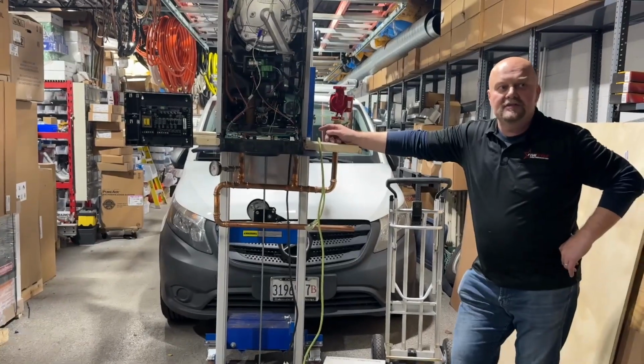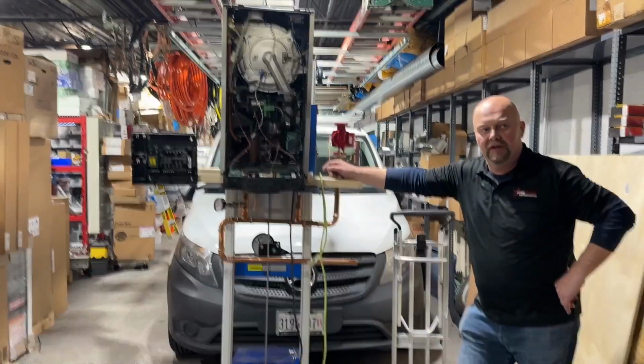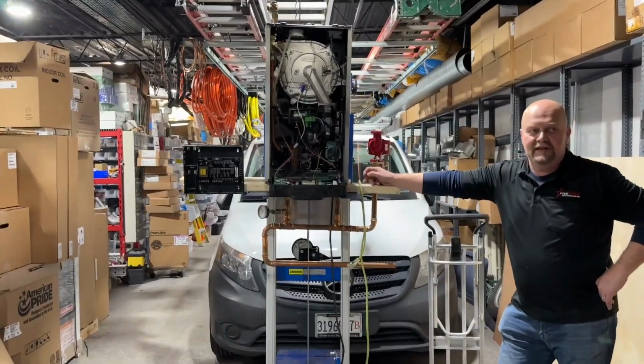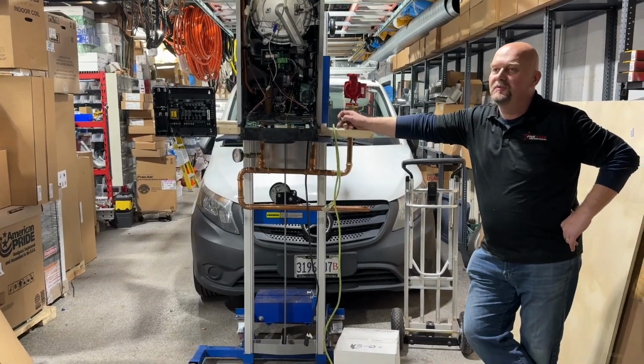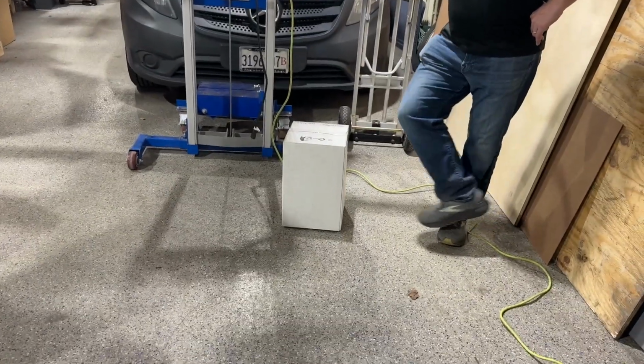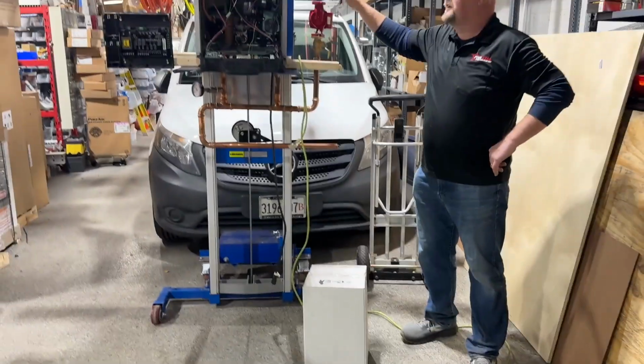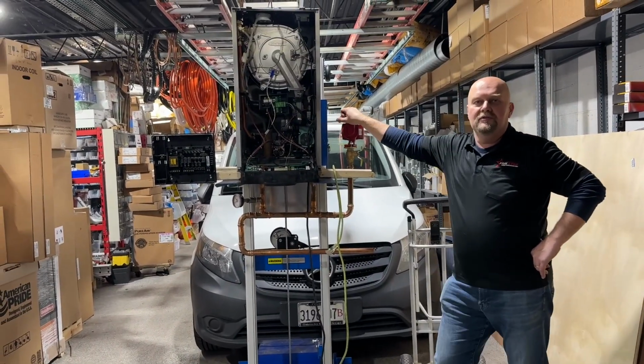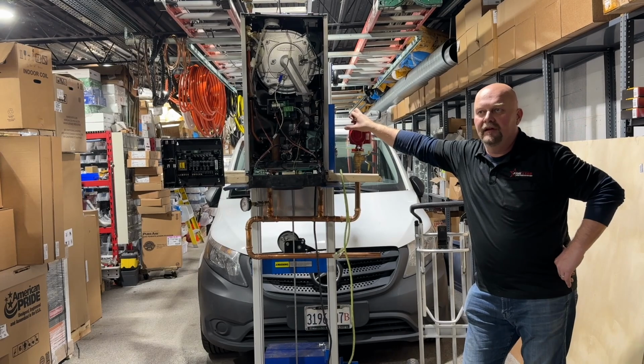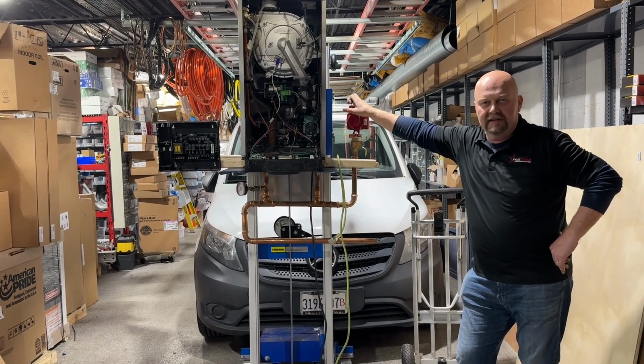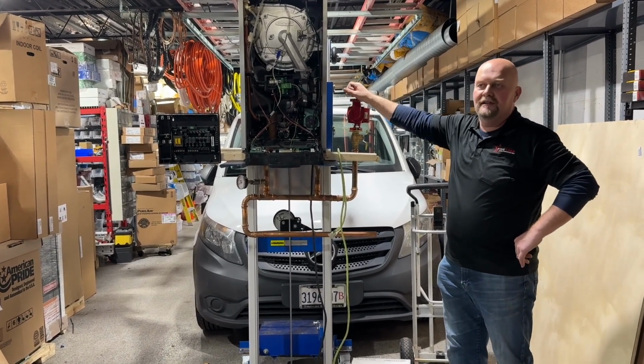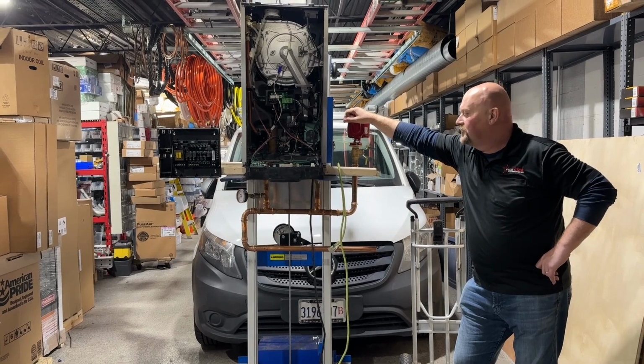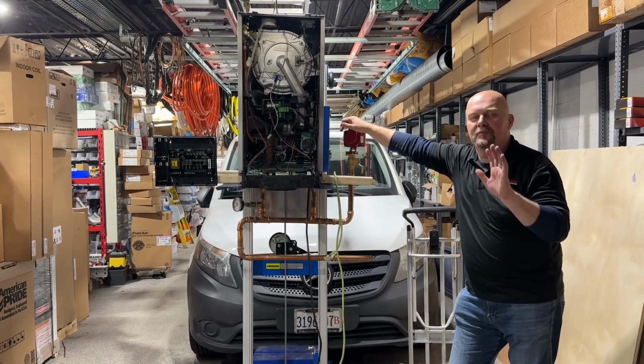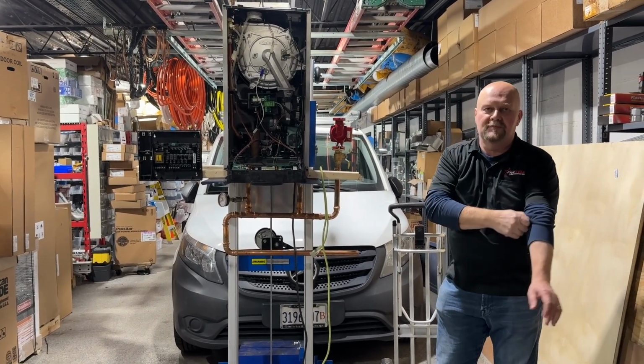Tank. This needs to be on the supply side of the boiler. The reason for that is less of a reason these days than it used to be. Back in the days when they were air tanks, the ones that would hang up on the ceiling, if you had it on the negative side of the pump, you would end up usually sucking air out of it, because it was full of air on top. You typically would want to, but let's always try to put it on the supply. They're meant to be on the supply side.